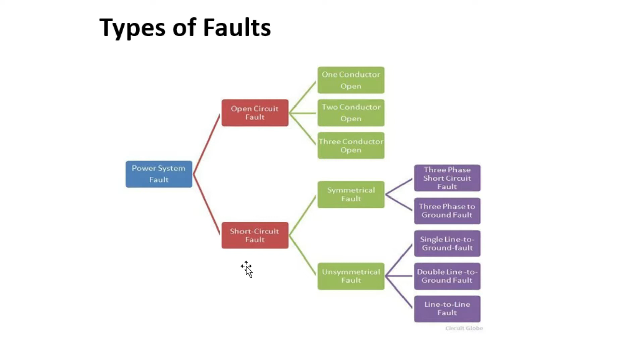So students, first coming towards our open circuit fault, what is the open circuit fault? The open circuit fault mainly occurs because of the failure of one or two conductors, and the open circuit fault takes place in series with the line, and because of this it is also called a series fault. Such types of faults affect the reliability of the system, and the open circuit fault is categorized, as you can see here in the figure, as a single phase open circuit fault, a two phase open conductor, or a three phase open conductor.